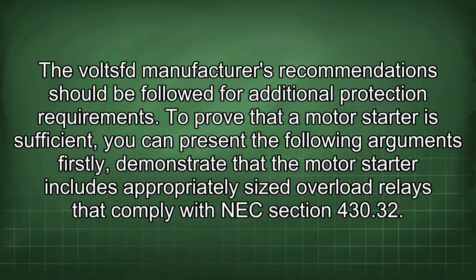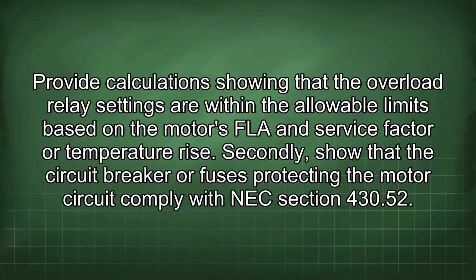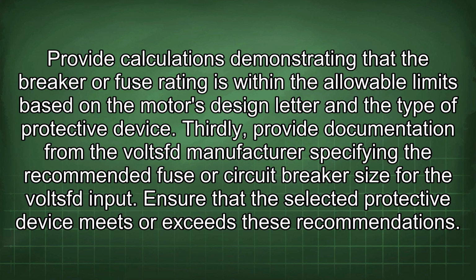Firstly, demonstrate that the motor starter includes appropriately sized overload relays that comply with NEC section 430.32. Provide calculations showing that the overload relay settings are within the allowable limits based on the motor's FLA and service factor or temperature rise. Secondly, show that the circuit breaker or fuses protecting the motor circuit comply with NEC section 430.52. Provide calculations demonstrating that the breaker or fuse rating is within the allowable limits based on the motor's design letter and the type of protective device.